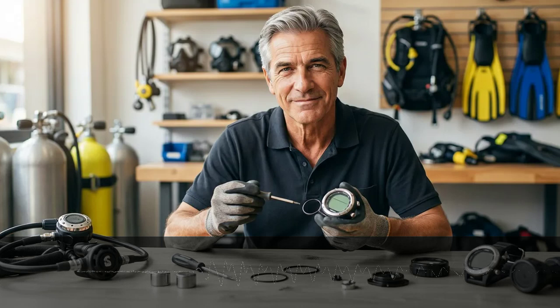Here's your condensed checklist to run through before any dive trip. I recommend printing this, laminating it, and keeping it with your gear. Battery and power. Make sure battery charge or life is above 50%. Bring a spare battery for user-replaceable models. All O-rings should be inspected and lubricated within 6 months. Computer powers on and completes self-check.